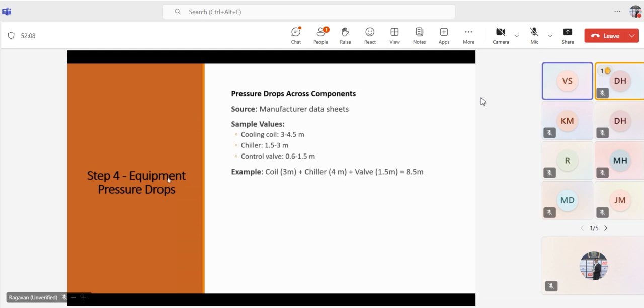Okay, yes. So you can see this, the equipment pressure losses. Usually, equipment pressure losses we will get from the manufacturer data sheet. According to the manufacturer data, you can obtain the pressure drop values for all components. This value should be added to the overall pressure drop calculation. For example, I have some values there. You can see this one, the value.